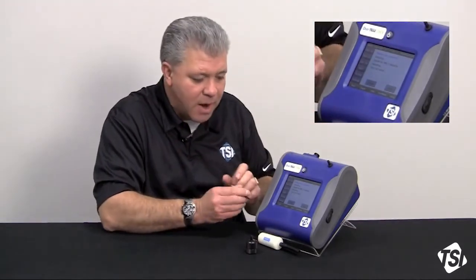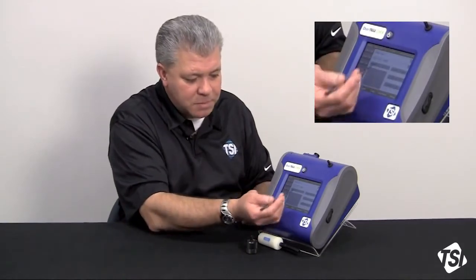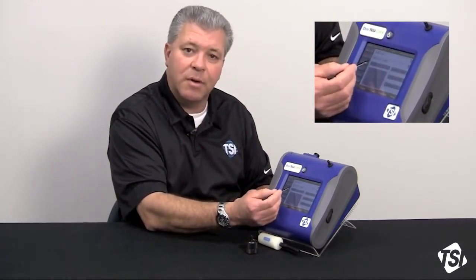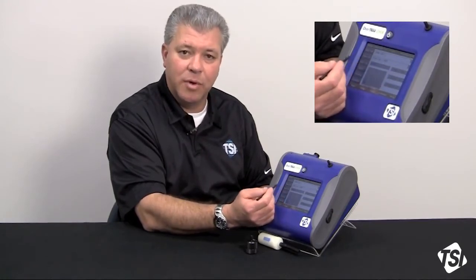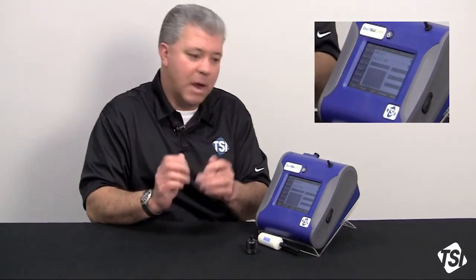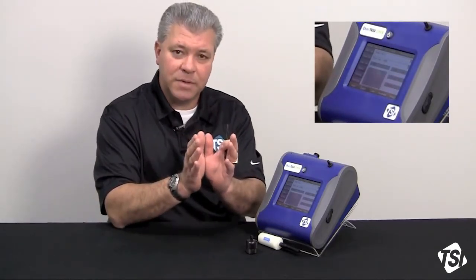Now, when this process is done, you're going to come back to this main screen, and instead of 1.0, there's going to be a correction factor put in there. I typically tell people that if it's within plus or minus 5% of 1.0, I would just leave the correction factor at 1.0. You're really not going to change the instrument's response at all. But if that correction factor comes up less than 0.95 or greater than 1.05, meaning you're starting to get a window of difference in accuracy where it's more than a 10% delta, you'd want to accept that information.